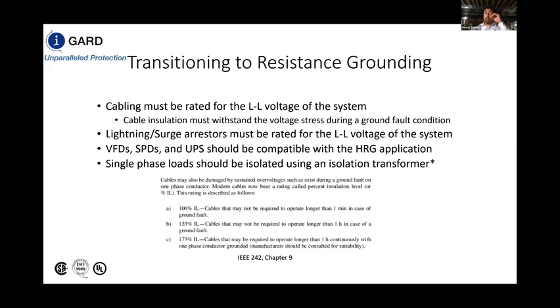When it comes to insulation levels for cabling in high resistance grounded systems, for systems up to 5 kV, you don't need to worry about what IEEE 242 says, because most cabling is already taking into account 173% insulation level rating, where you can hold the fault for longer than 1 hour continuously. In the case of low resistance grounding, where it's utilized on higher kV values, let's say 15 kV or 13.8, consultants can use either 100% or 133%, depending on how long they're leaving the fault in the system. But usually for these higher voltage systems, they're typically tripping on first fault and coordinating accordingly with their feeder circuits downstream to isolate the point of fault before the main circuit breaker upstream trips.